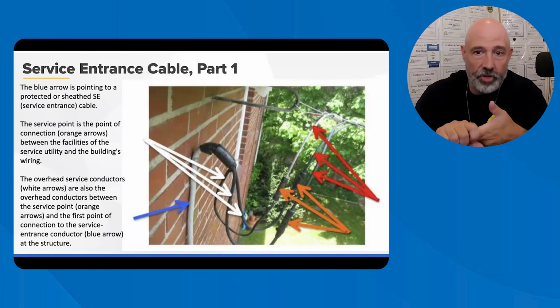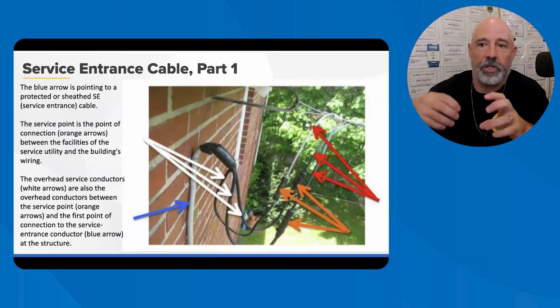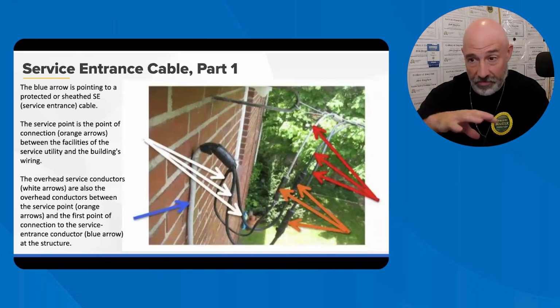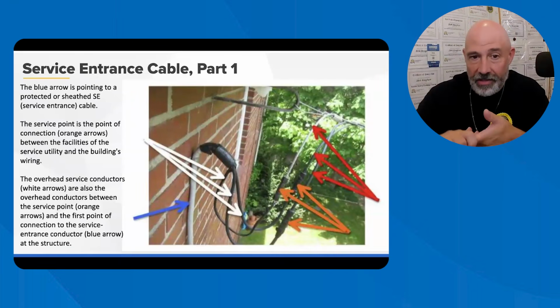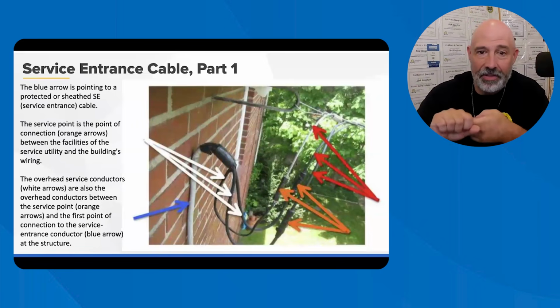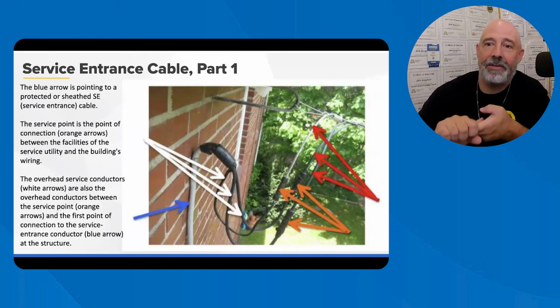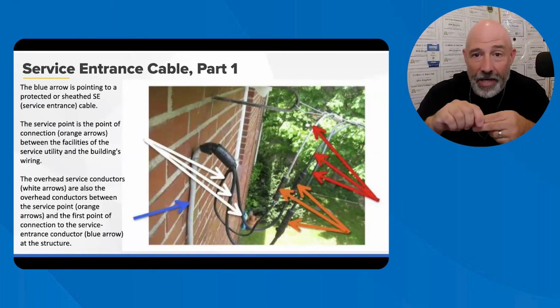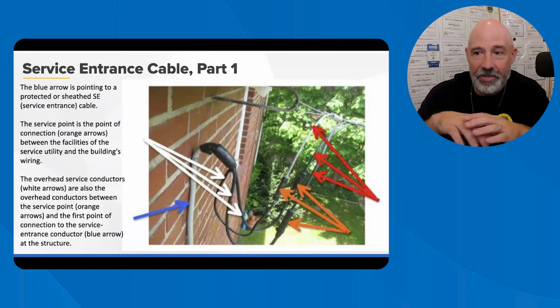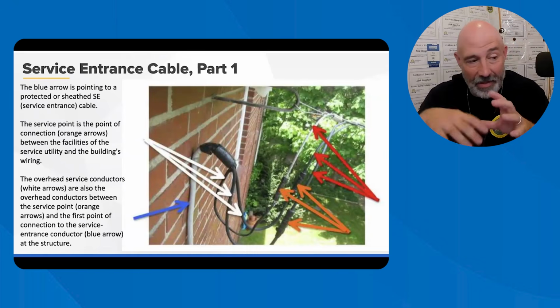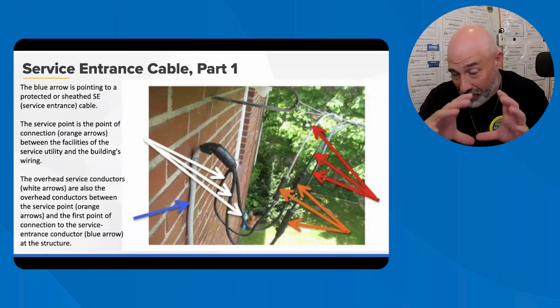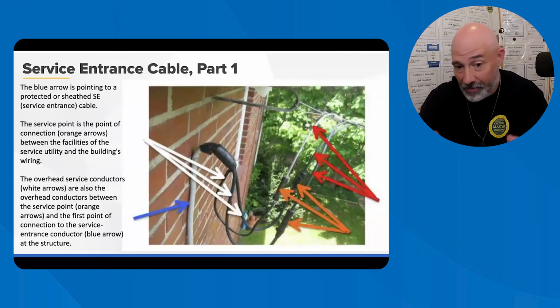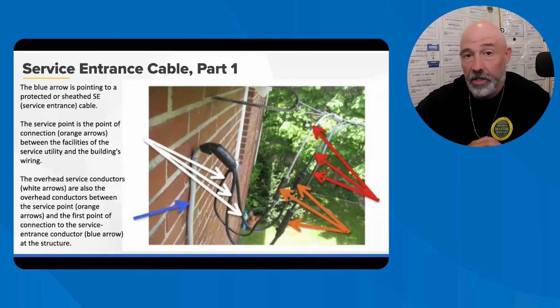The fitting and enclosure housing service conductors are also part of that service equipment. The meter socket and the enclosures are not considered service equipment. Meter enclosures do not have interrupting ratings, no disconnecting means or overcurrent protection. And if you ever go to a meter, you will know that the only way to shut that off is by pulling that off or contacting the utility company to shut it off at their hub.